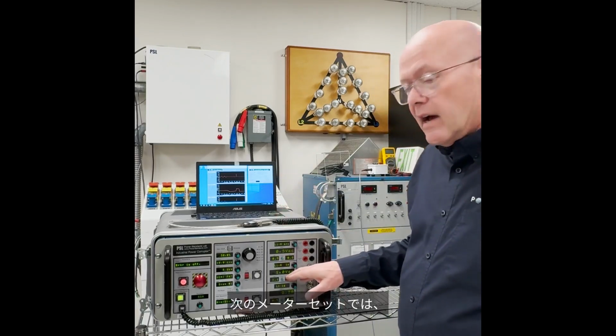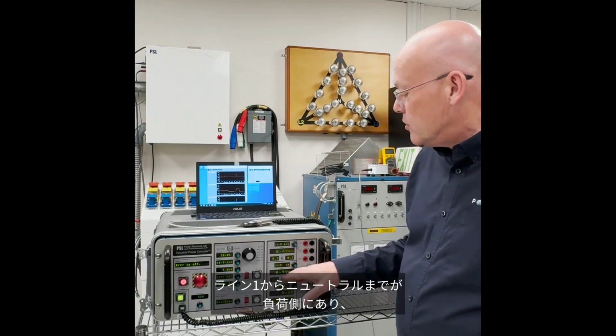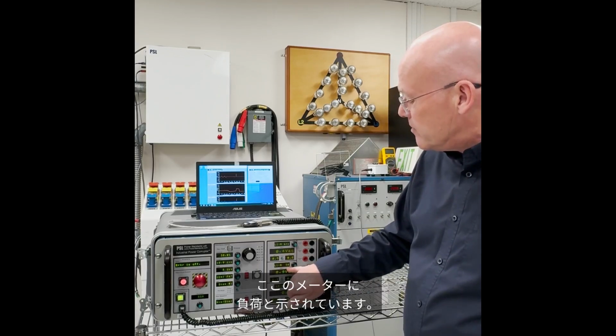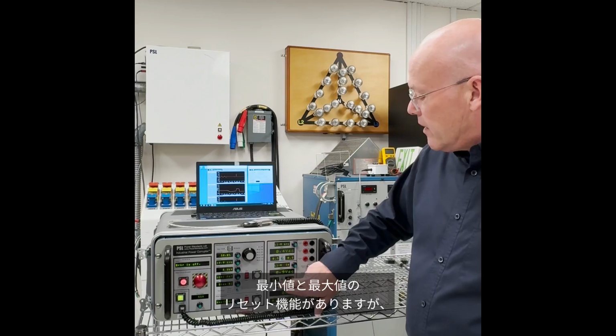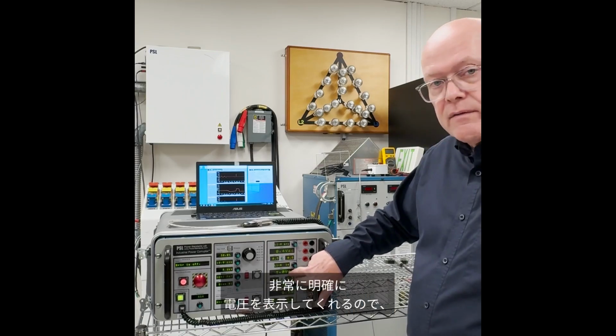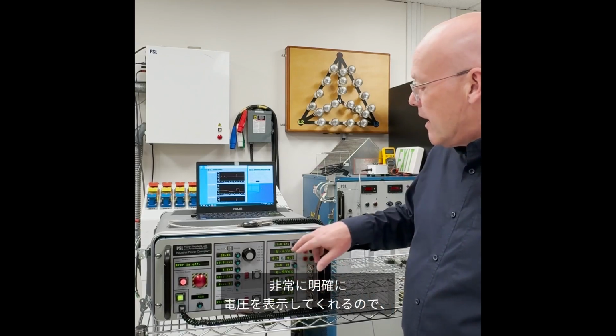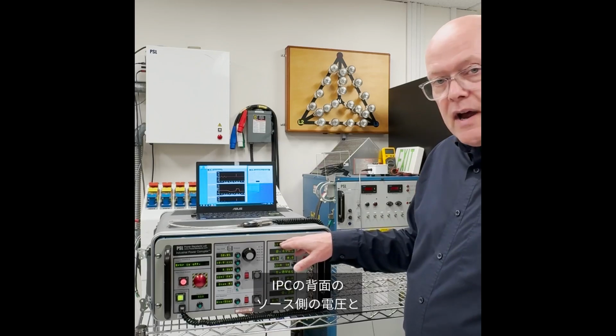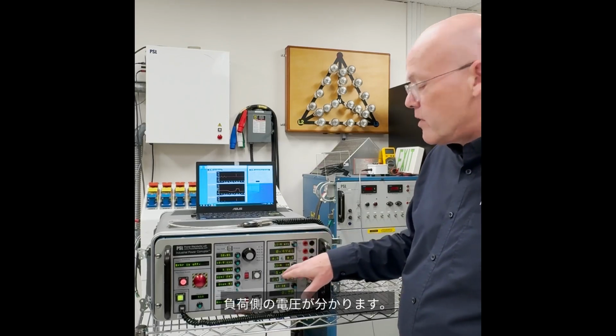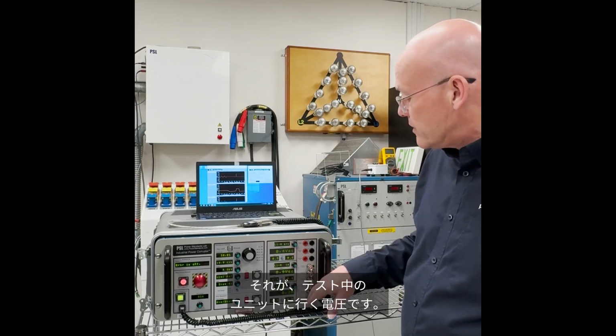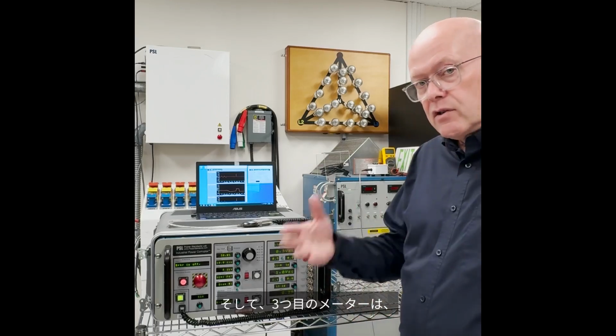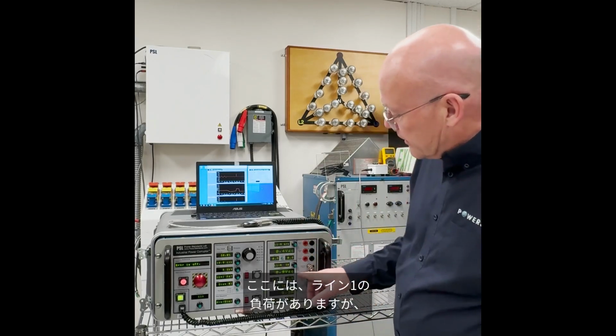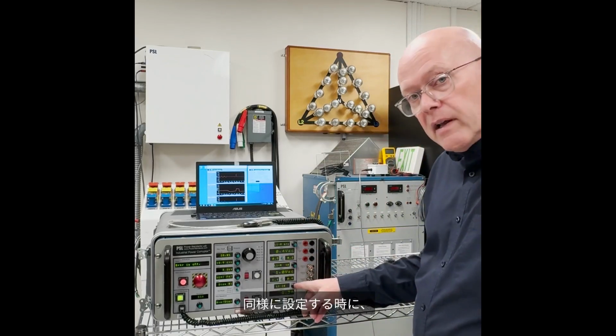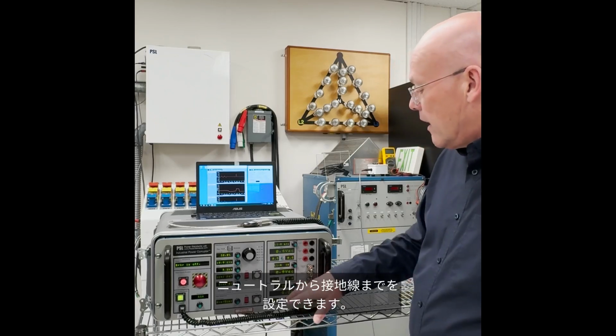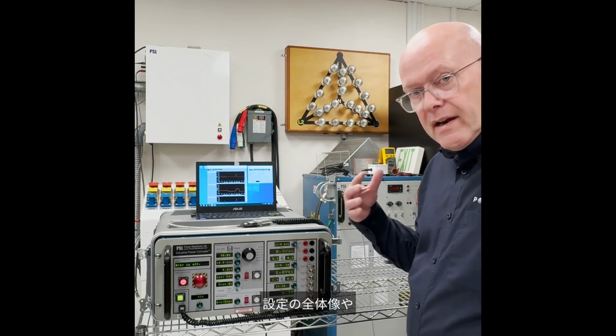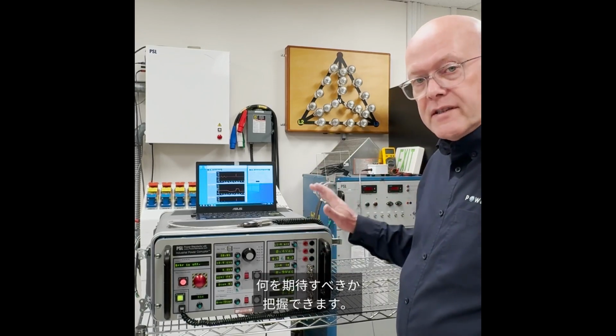For the next set of meters, we have line 1 to neutral, but on the load side, and you can see indicated on the meter here, it says load, and again, there's reset capability for min and max. It will give you your voltage so that you can see very clearly what voltage you have on the source side at the back of the IPC and what you have on the load side that's going to your unit under test. And then the third meter, you can use that to supplement information. Here we have line 1 load, but equally when you set up, you could have neutral to ground. You could have a number of other parameters that gives you a full appreciation of the setup and what to expect.